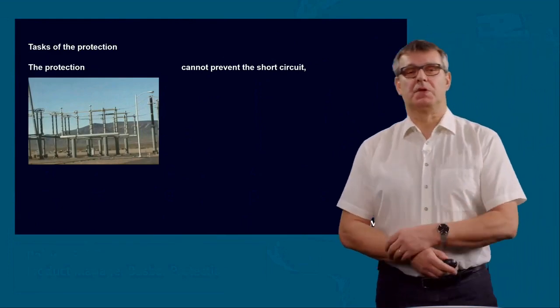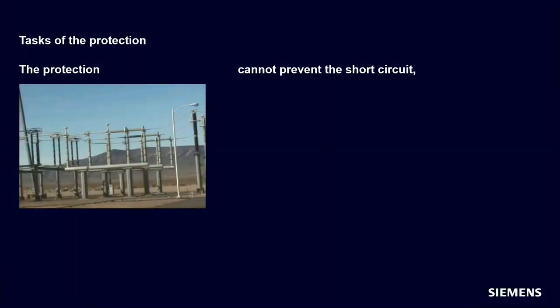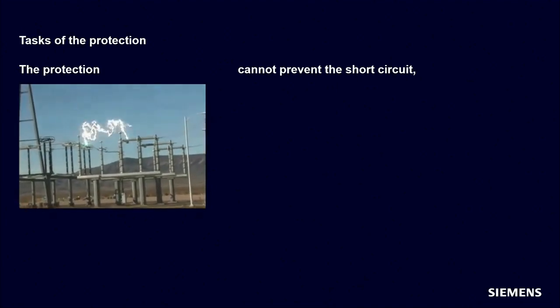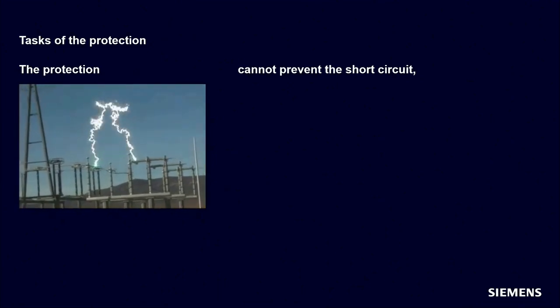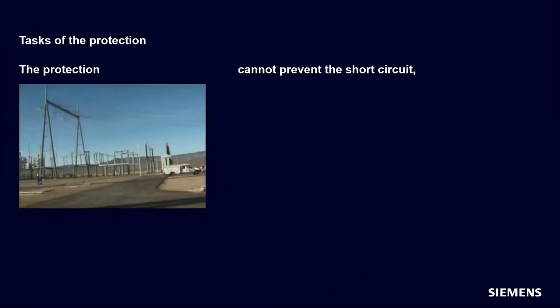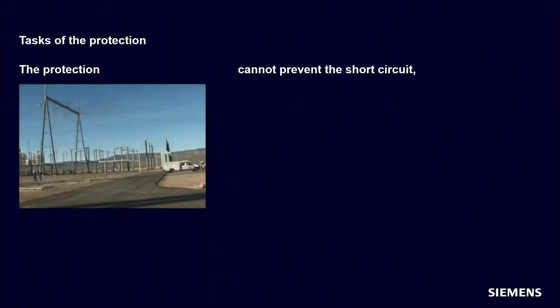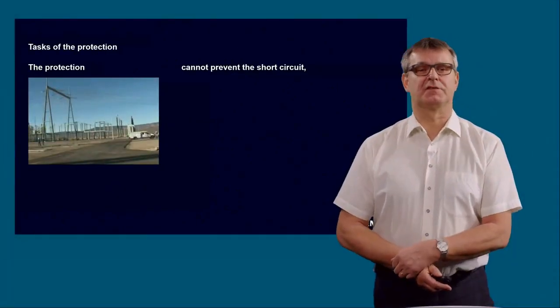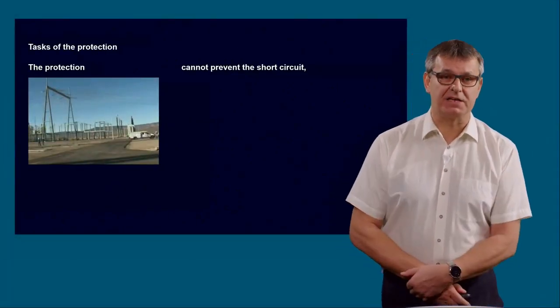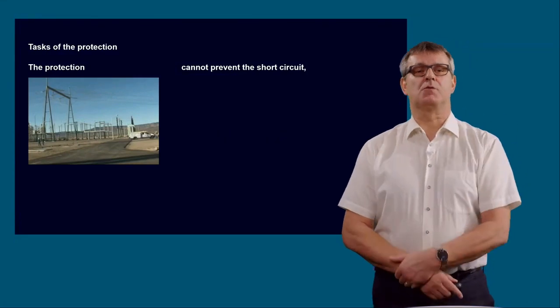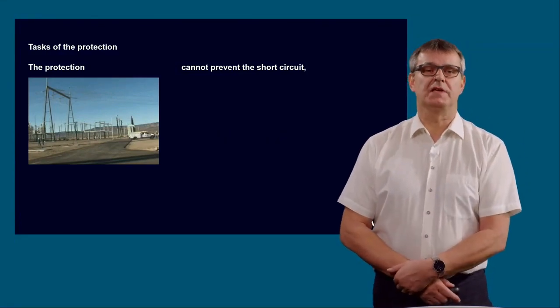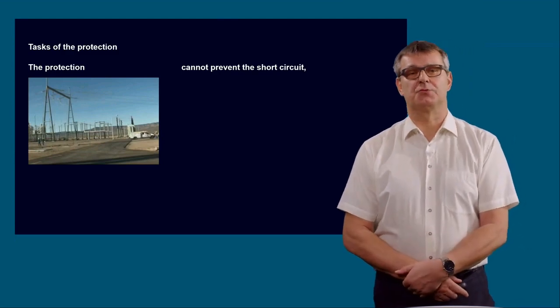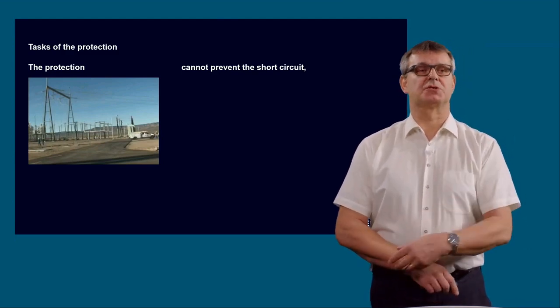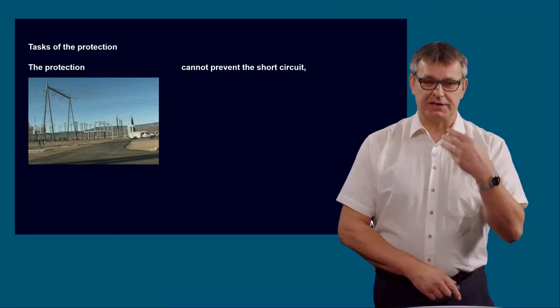Task of protection. The protection cannot prevent the short circuit. I guess you know it. Let's see this small video. What we have seen here is a so-called evolving fault. It started, from the busbar protection point of view, as an external fault. We have seen a very strong arcing, and the busbar was on the top of this small video. And as soon as this external arcing reached the busbar, the busbar protection immediately cleared the fault.